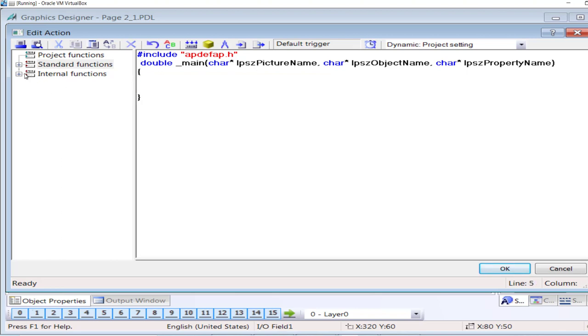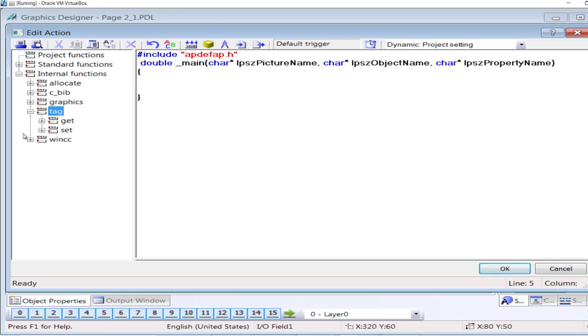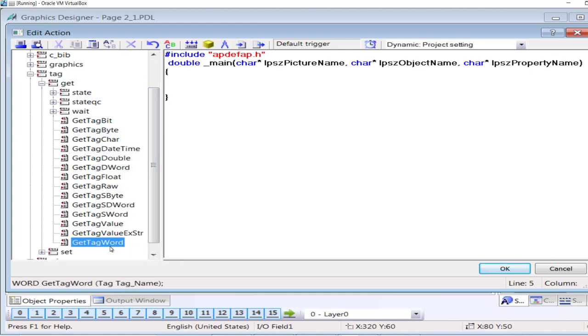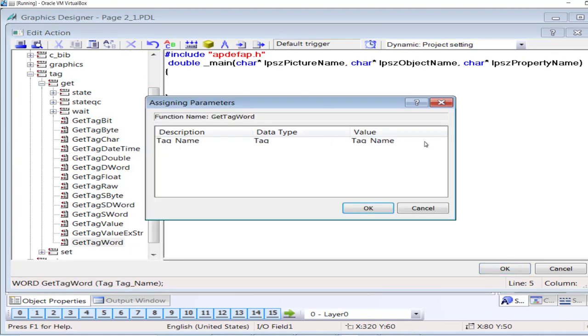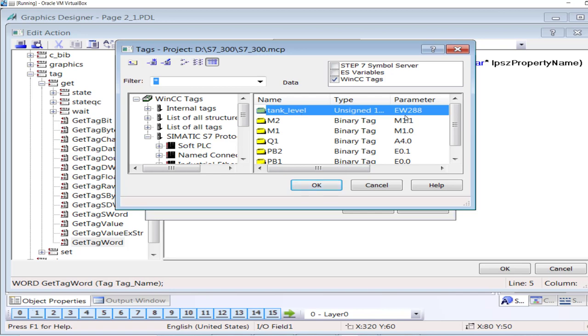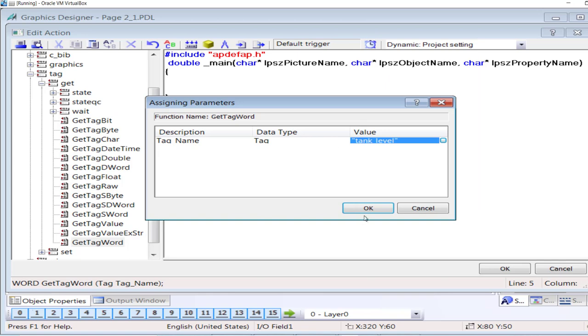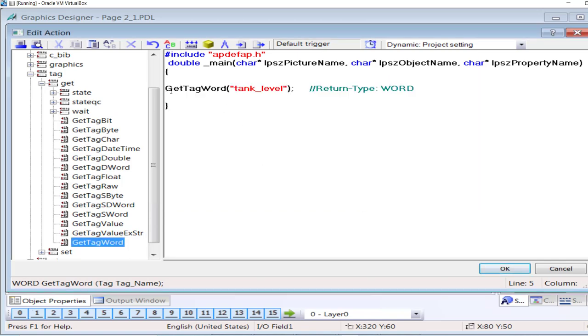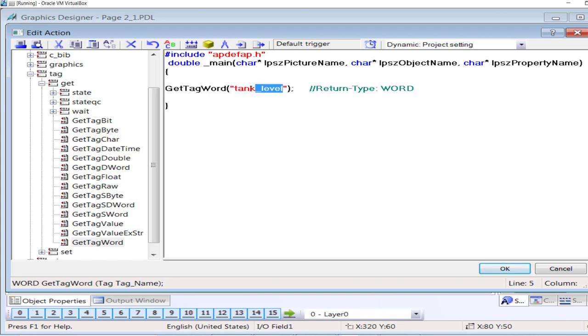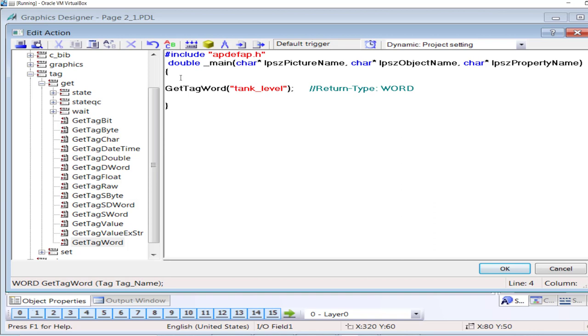Now the output value would be accessed through C script. In the internal functions we have GetTagWord. I will import the analog tag that is addressed IW 288. Now let me tell you about the prototype. GetTagWord is the name of the function, while Tank Level is the analog tag that would be accessed by this GetTagWord function. The value is returned here.